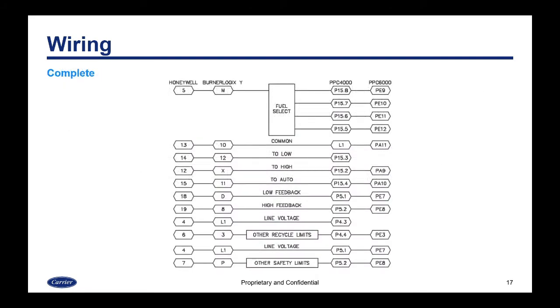So this is the complete wiring interface between the two. It lists all the terminals that are common between the Honeywell and the Burner Logix. They each have terminals with the same functionality, but different terminal numbers. And the PPC4000, 6000 as well, different terminal numbers, but most of the terminals are the same.